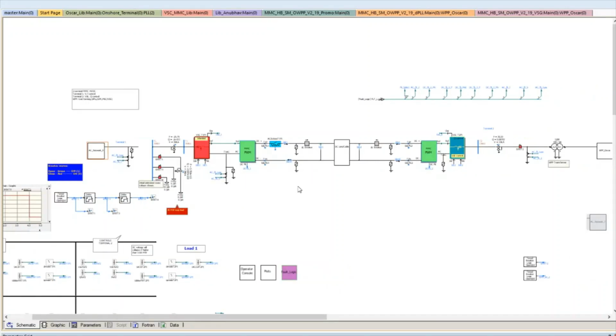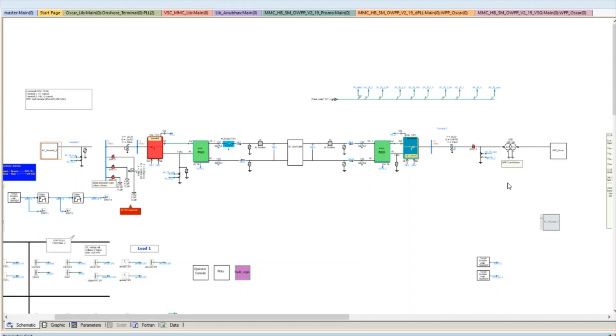In the normal mode, you would have the onshore grid connected, and the onshore MMC would operate in VDC-Q control. So it would control the DC link voltage of the HVDC link and the reactive power injection into the onshore terminal. And the offshore terminal would be responsible for controlling the offshore voltage and frequency. So it would be working in islanded operation, to which the grid-following wind turbines would then connect.